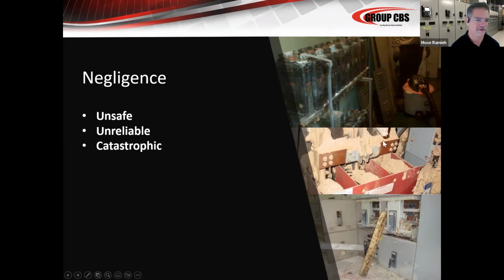I mean, once again, you can see the sawdust in this picture. Will this Pringle switch open? Maybe it will, maybe it won't, right? It's kind of a 50-50 shot. And even if it does open, we've got combustible material all piled up in this breaker. So could this catch fire? Sure. If there were to be an arc flash event, could it be even more catastrophic?